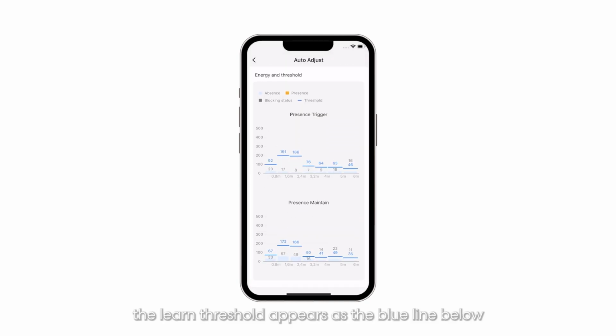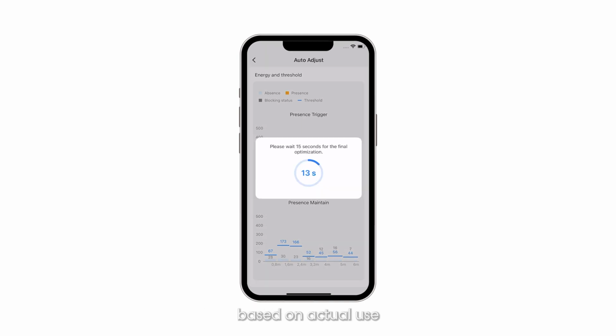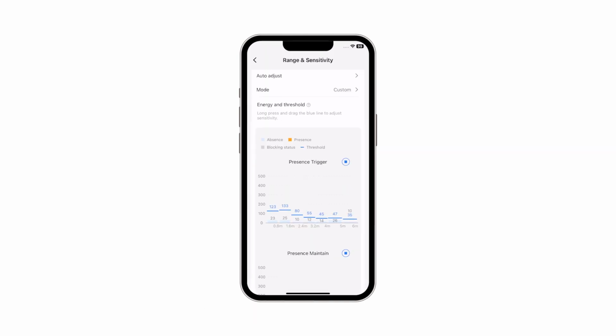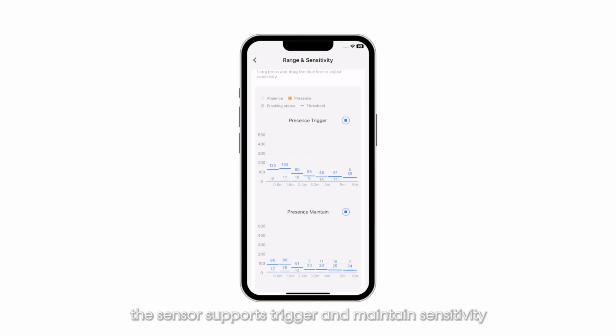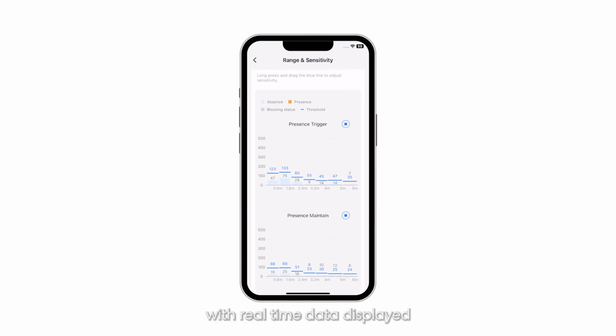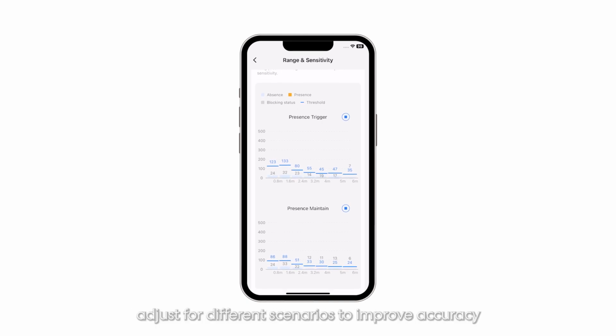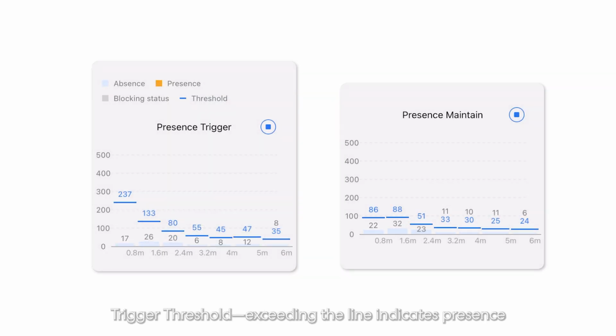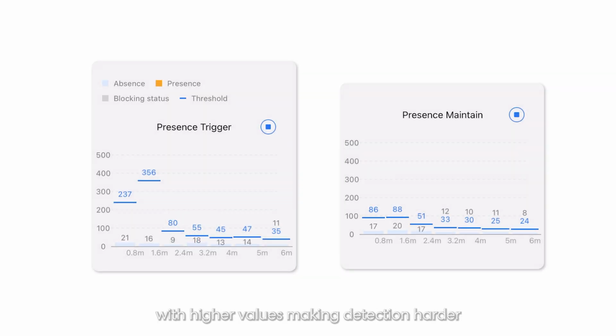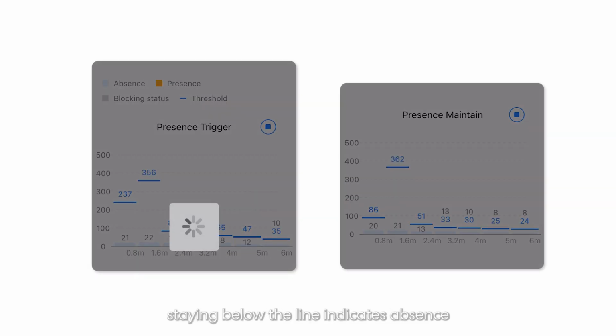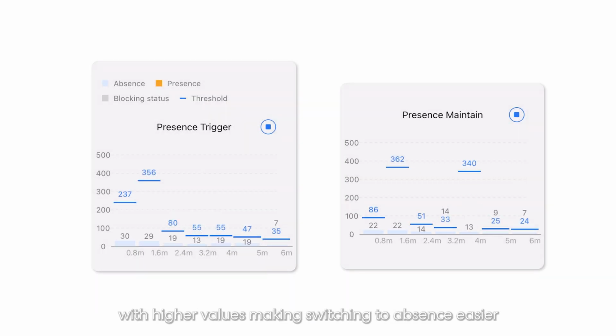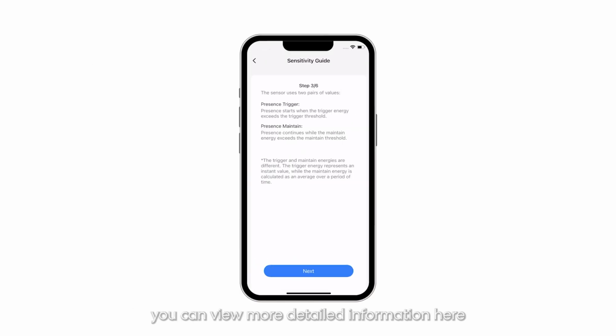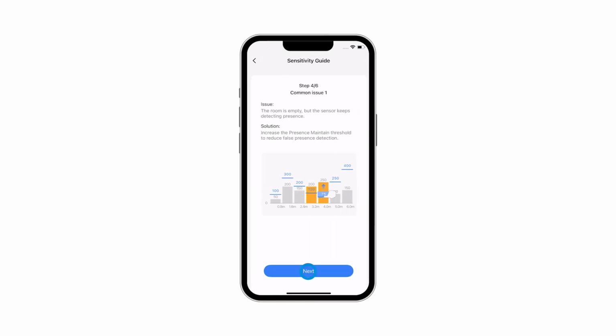The learn threshold appears as the blue line below and can be long pressed to fine-tune based on actual use. The sensor supports trigger and maintain sensitivity, with real-time data displayed. Adjust for different scenarios to improve accuracy. Trigger threshold exceeding the line indicates presence, with higher values making detection harder. Maintain threshold staying below the line indicates absence, with higher values making switching to absence easier. You can view more detailed information here.